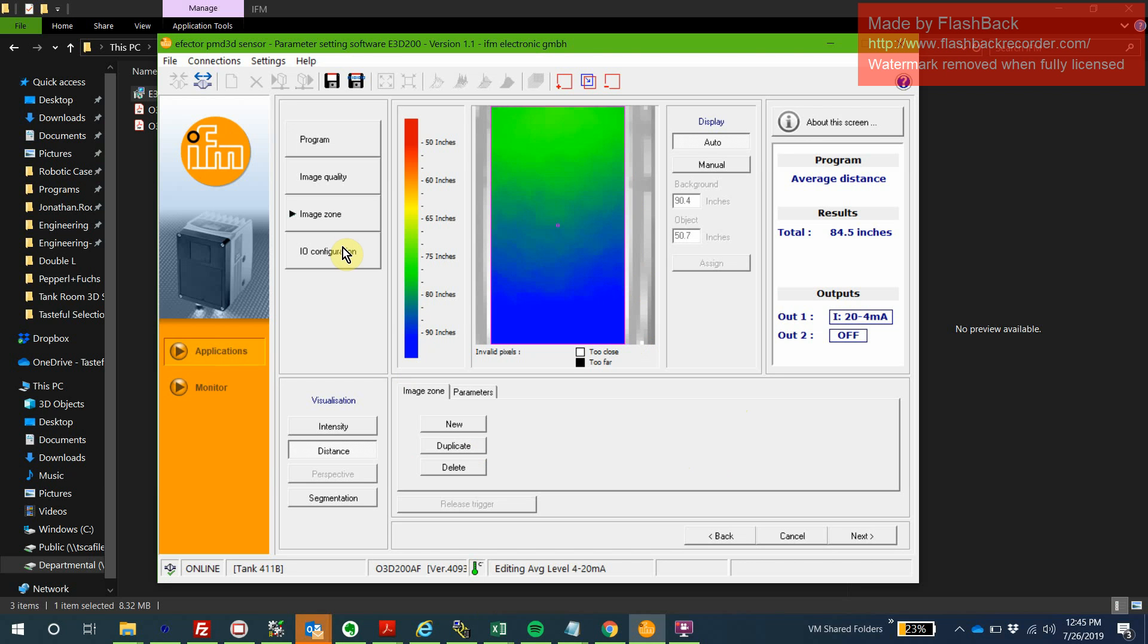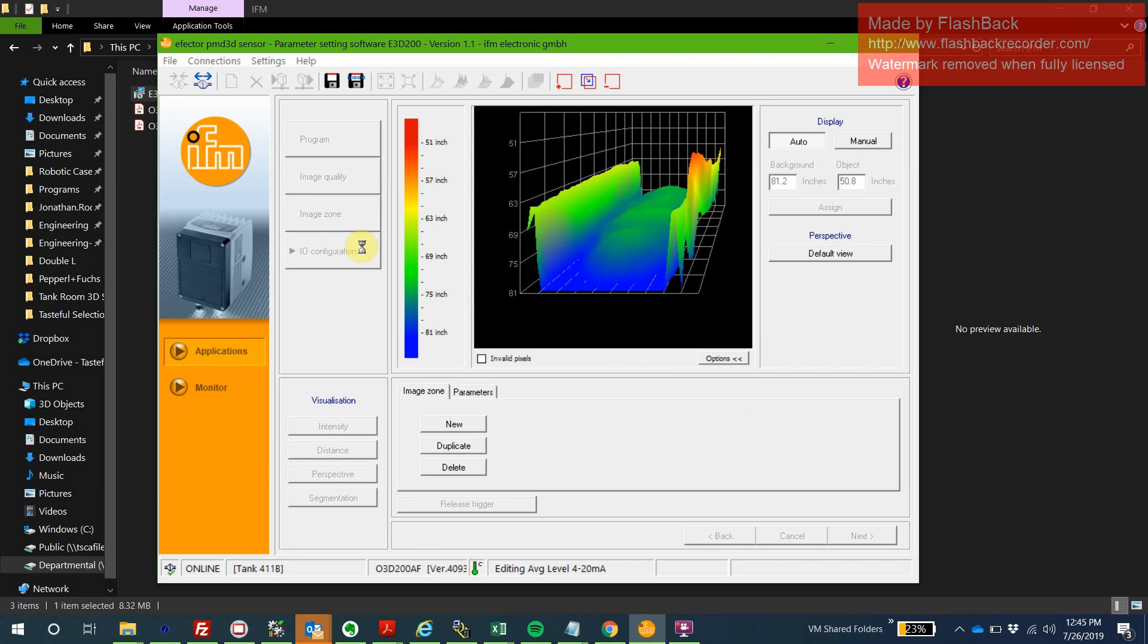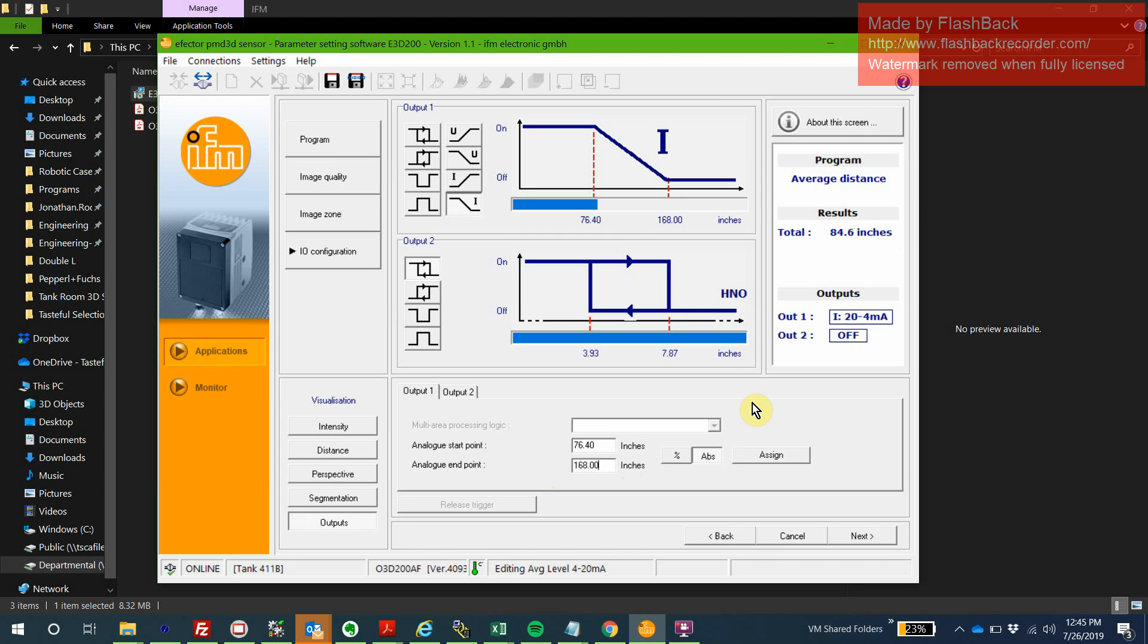What we're really looking for here is IO configuration. Here, these are our set points. This is what we're actually reading right now, and this is where we want to enter this value if we want that to be our new set point. This is why we need to come out when the tank is full and come back when the tank is empty, because that's the only way we're going to get an accurate value as to what the sensor is going to read at those levels.